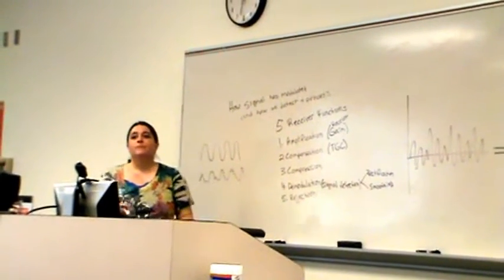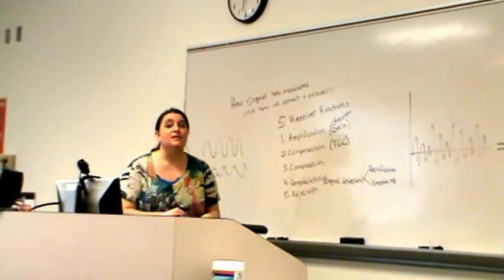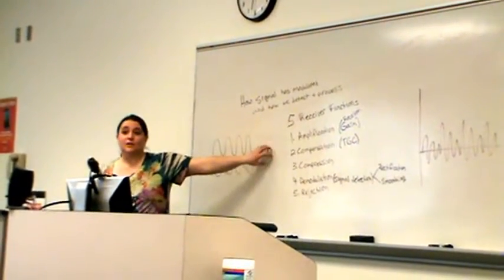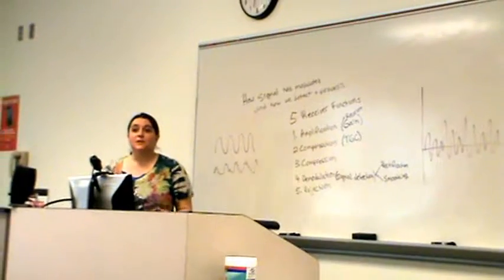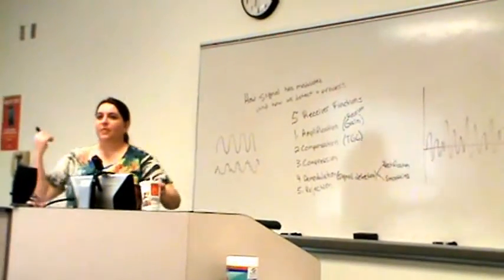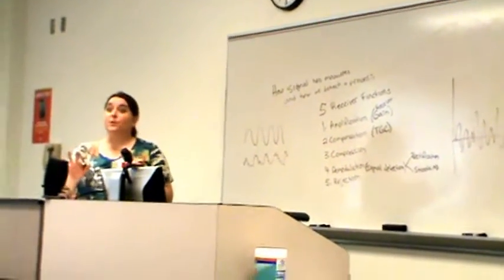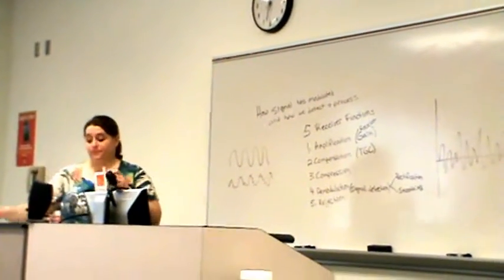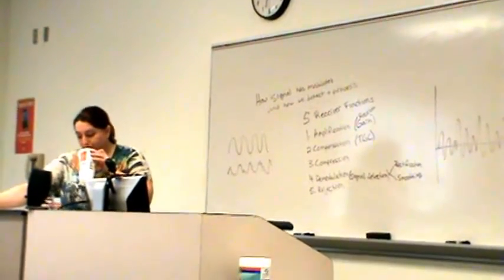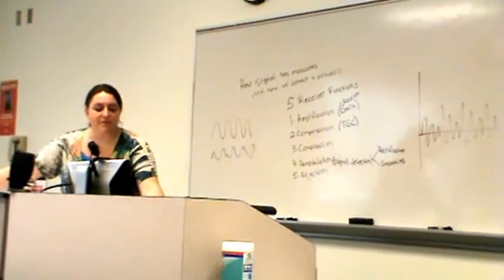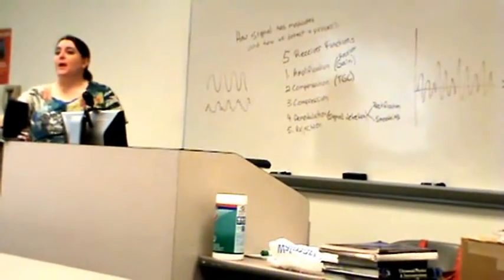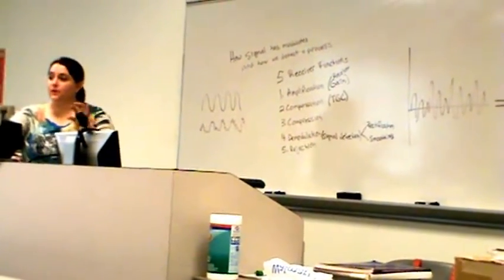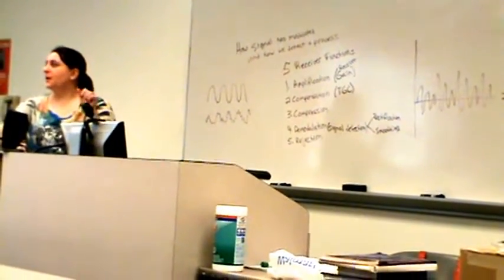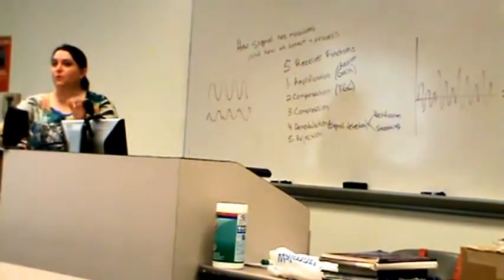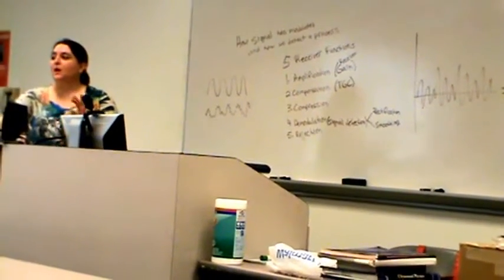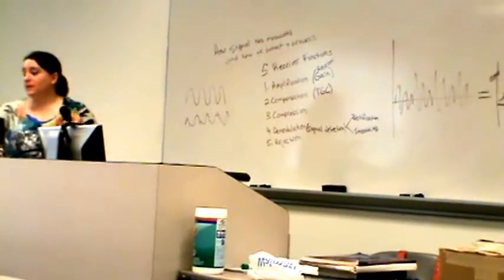So is it post-processing? It's technically supposed to be pre-processing because gain is here in this receiver function, but newer systems have taken that out. So for testing purposes, it's still pre-processing. The rule of thumb is, if you freeze the image and you can still change something, like the compression knob, and there's a couple of things that you can still change with the image frozen, that's post-processing. If you freeze it and the knob no longer works, that's a pre-processing knob.